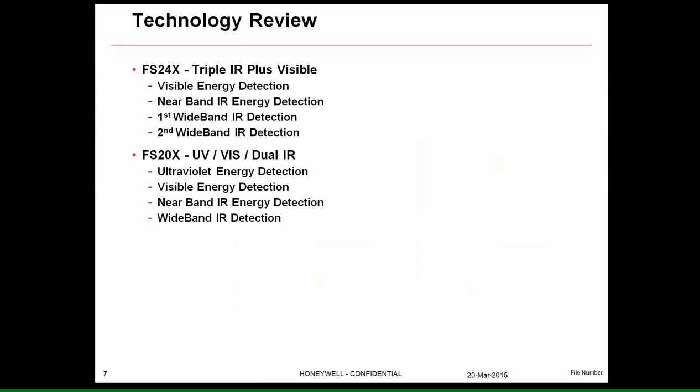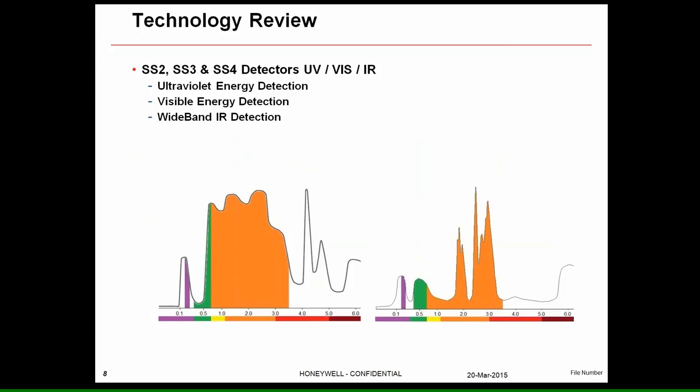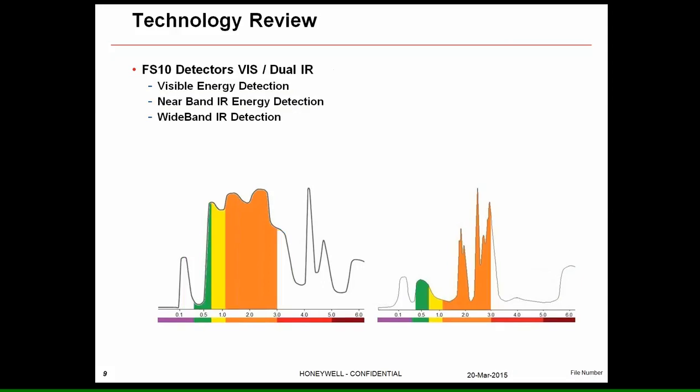When we talk about the technology we use, the triple IR plus looks at the visible region, near-infrared, and two separate wide bands. Our UV/IR is actually a UV dual IR — it looks at ultraviolet, visible, and near-infrared energy, plus a wide-band infrared section. These are all broad-spectrum regions, not narrow bands — very broad bands of energy that we look at.